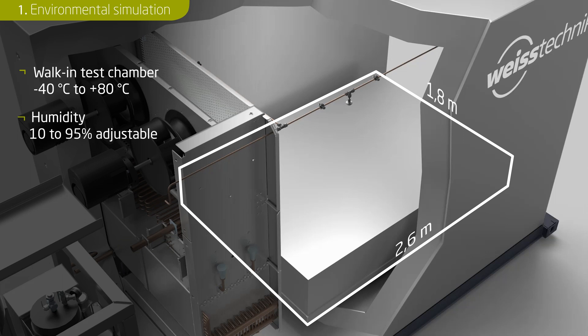If, for example, the test chamber contains an 800-kilogram battery pack and a 200-kilogram test rack, the temperature gradient would only be 3 Kelvin per minute. In this test scenario, it would therefore take less than 20 minutes to heat up from a room temperature of 22 degrees Celsius to 80 degrees Celsius.